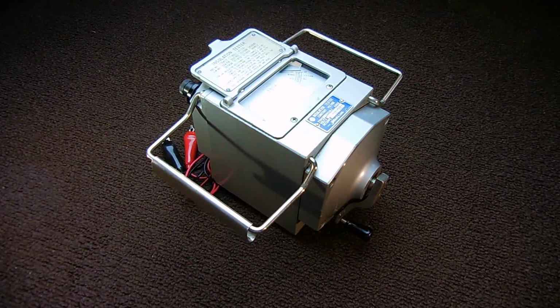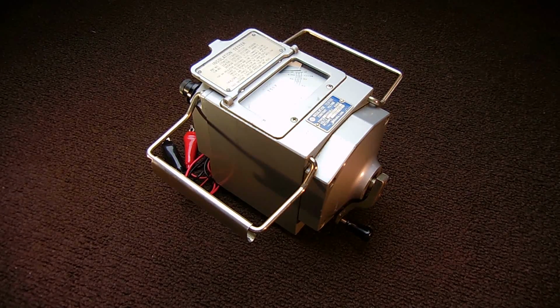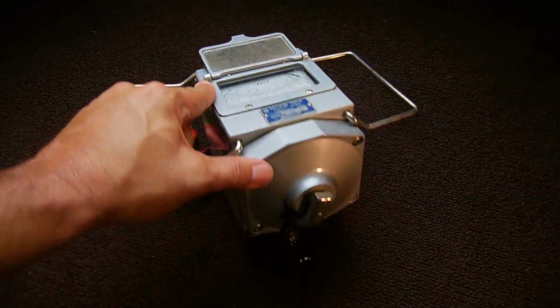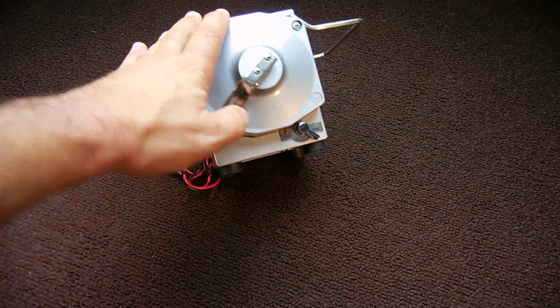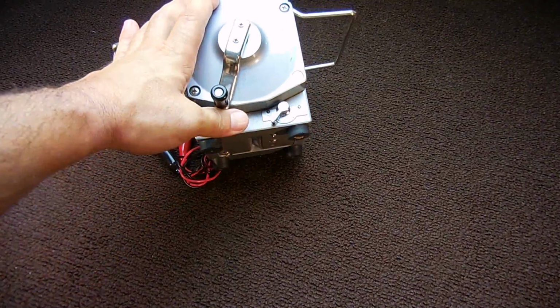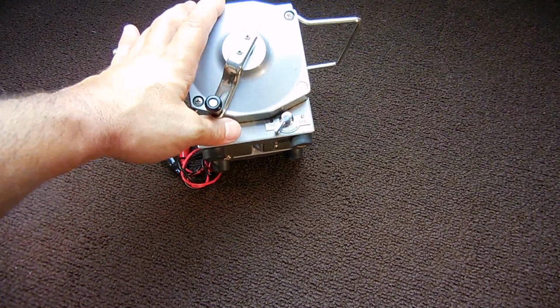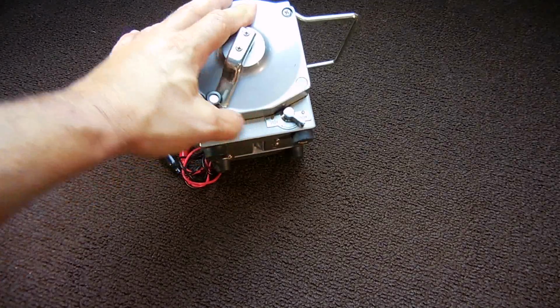Now generally, when you're doing testing, it's a good idea to test with a voltage that's twice as high as the voltage that's being used for a particular motor or heating element. So if you're going to be testing a motor that operates at 120 volts or a heating element, or you just want to check some wires out that are possibly grounding out, you're going to set it to the 250 volt scale, which will be right here. If you're working on a 240 volt circuit, you're going to push it over to 500.